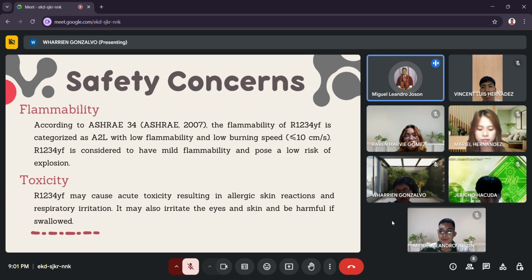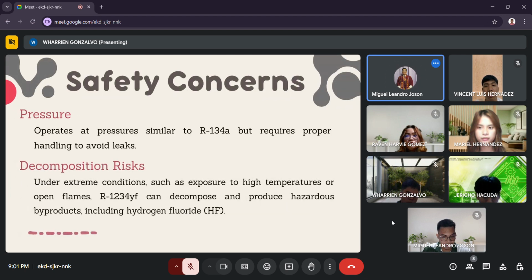Toxicity. R1234yf may cause acute toxicity resulting in allergic skin reactions and respiratory irritation. It may also irritate the eyes and skin and be harmful if swallowed. Next we have the pressure. It operates at pressure similar to R-134a but requires proper handling to avoid leaks. Next, decomposition risk. Under extreme conditions, such as exposure to high temperatures or open flames, R1234yf can decompose and produce hazardous byproducts, including hydrogen fluoride.